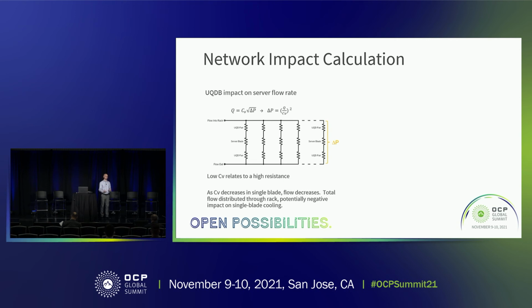Just as an example, let's say you have a rack with 8 servers in it, and you have extremely good, well-performing universal quick disconnects. Maybe they have a very high CV, right? Because we only specify a minimum. So maybe they have twice the CV that is required as a minimum for 7 of those, and then your 8th, both the inlet and the outlet pair, maybe they only meet that minimum CV value, right?